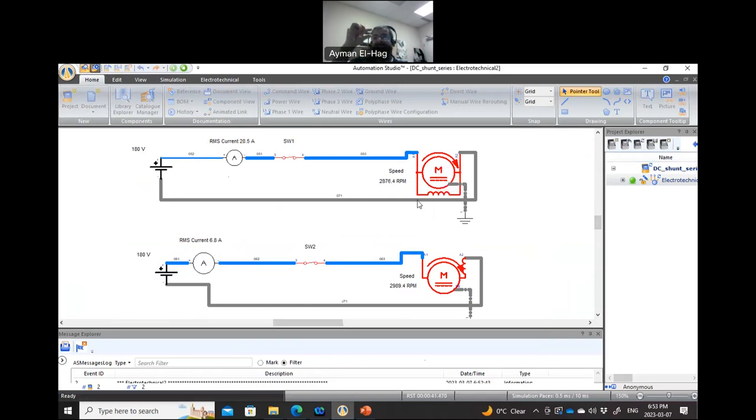There is a drop, but a slight drop in the speed. Now, let's go to the series motor and do exactly the same thing, make it 10, and see how much the speed will be affected. See here, it drops from around 3,000 to around 1,680. So it's a huge drop in the speed of the motor.